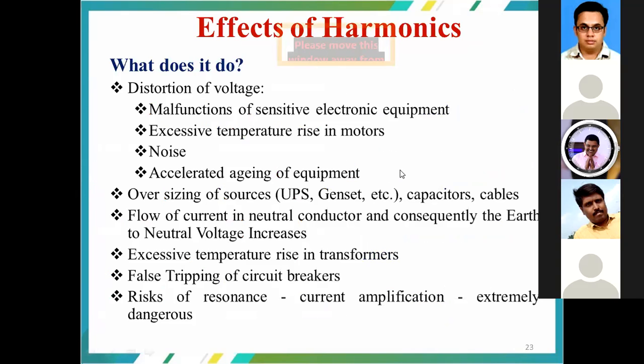And the ill effects of the harmonics are as listed. The first one is the distortion of the voltage, which results in malfunctions of sensitive electronic equipment, excessive temperature rise in the motors, and noise, that means the motor is not going to have smooth operation. Then it paves the way for accelerated aging of the equipment, which includes the cables, fuse units, MCBs, or the associated protective equipment.